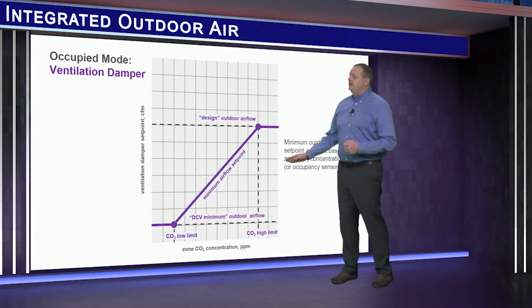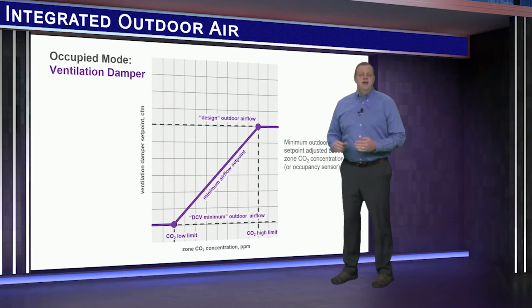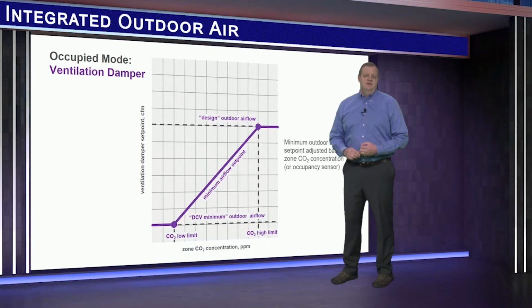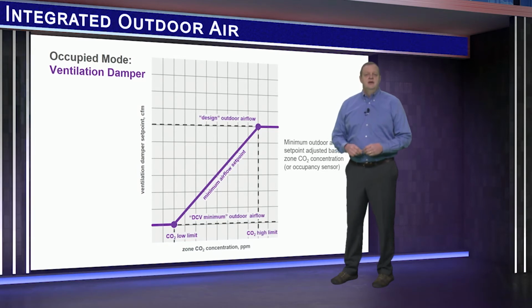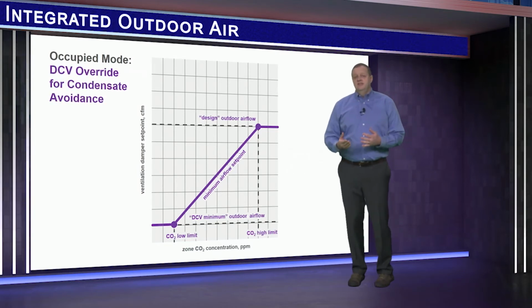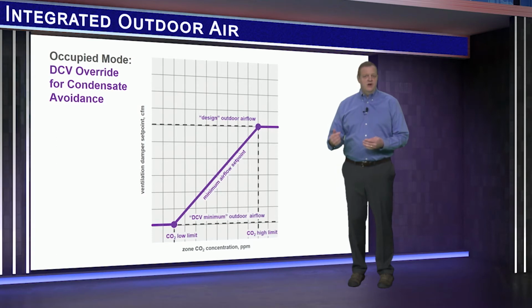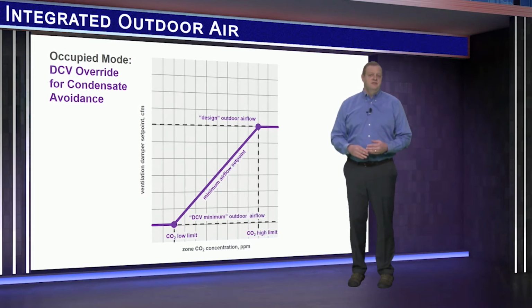So this purple line defines the minimum airflow set point for the ventilation damper. Most of the time, it's bringing in only this minimum airflow required for ventilation. But remember, in a sensible cooling system like CoolSense, this dry air from the dedicated outdoor air system is the only source of dehumidification. So when you decrease outdoor airflow with demand control, you're also providing less dehumidification.